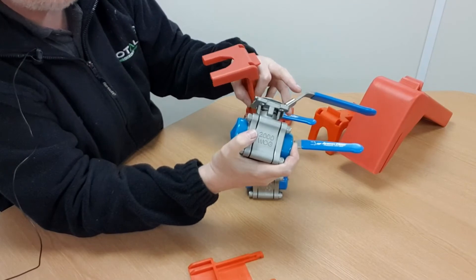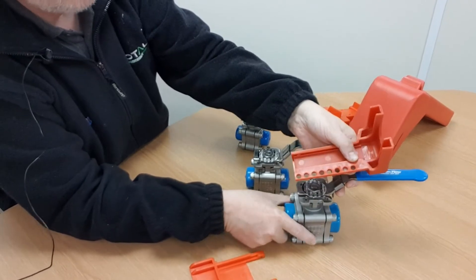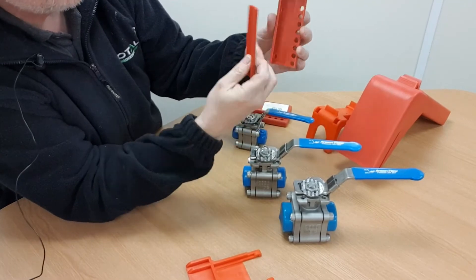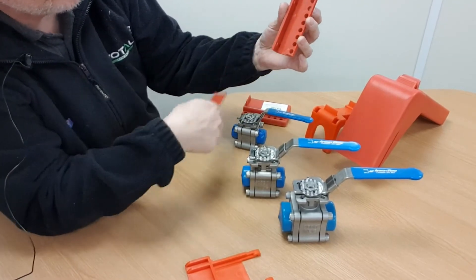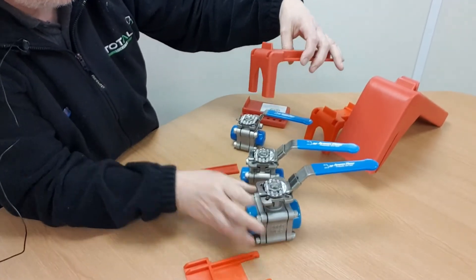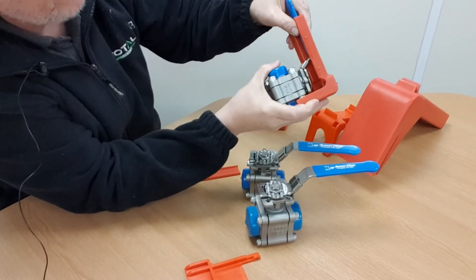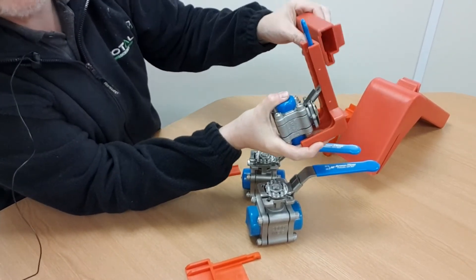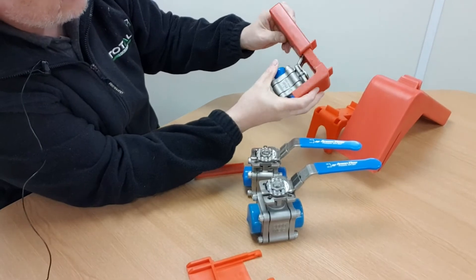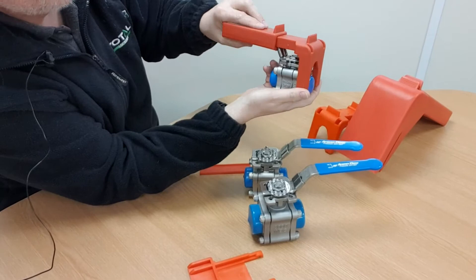That's not really a criticism of the locking device itself — it's recognizing that the design features of the top of the valve can vary and become troublesome for fitting the locking device. It's also worth noting that we've got this little removable sleeve. When you take out the sleeve, it increases the pocket size inside, making it easier to accommodate the valve lever. Once that's on, the other half of the device can slide down into place.